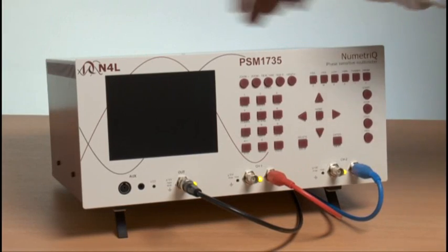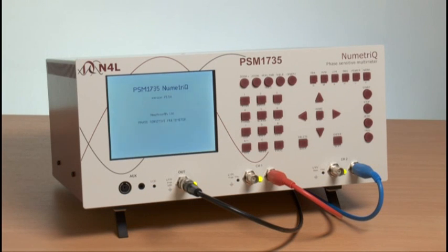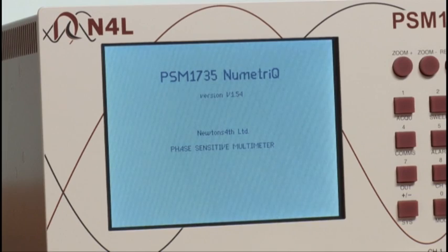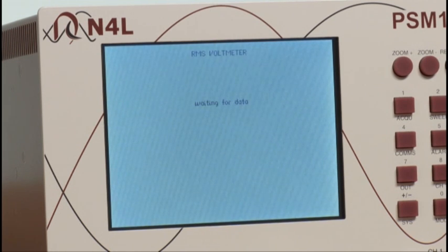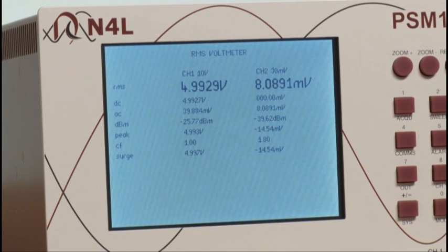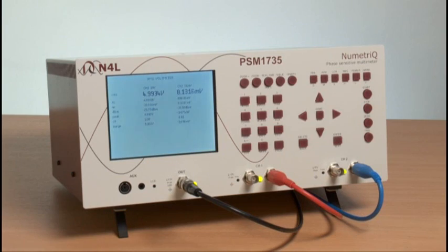If we now switch on the instrument, there will be a power-up routine. Then the default measurement screen will be presented showing RMS voltage measurements on each of the PSM 1735 measurement channels. Here you can see 4.99 volts, which is predominantly the DC voltage on one side of the injection resistor, and 8 millivolts, which is the AC component measured on the other side.